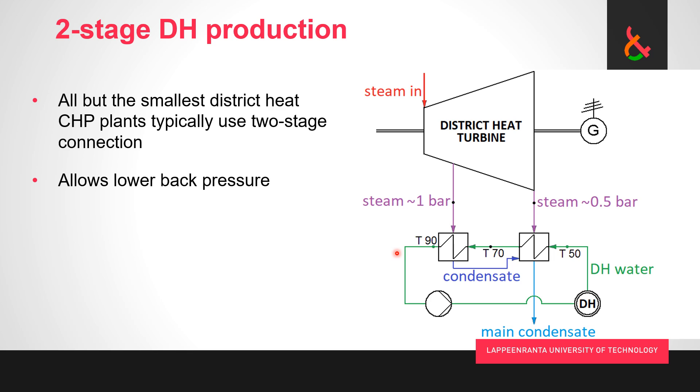Basically it allows us to have lower back pressure. If we had single stage, if we wanted to produce 90 degrees district heating water, it would mean that our expansion would stop here at one bar. We would have no option of expanding any further. Now we let half of the steam expand further to preheat the district heating water halfway up.